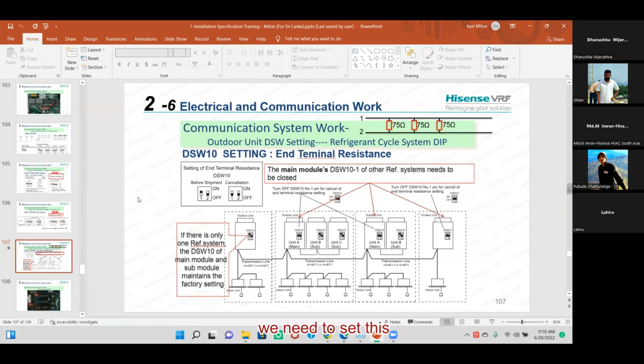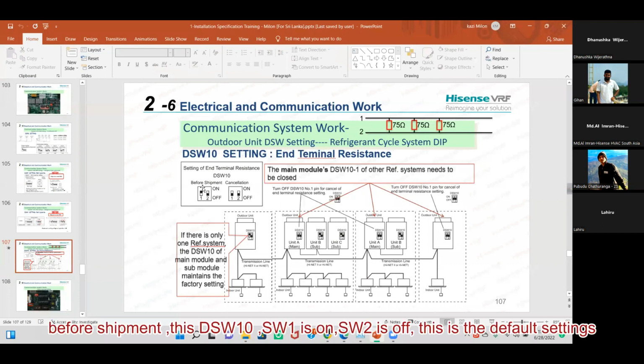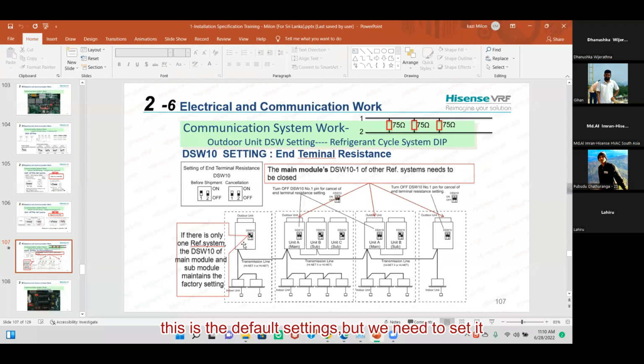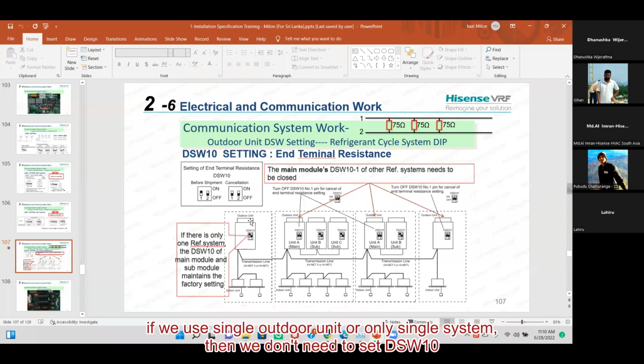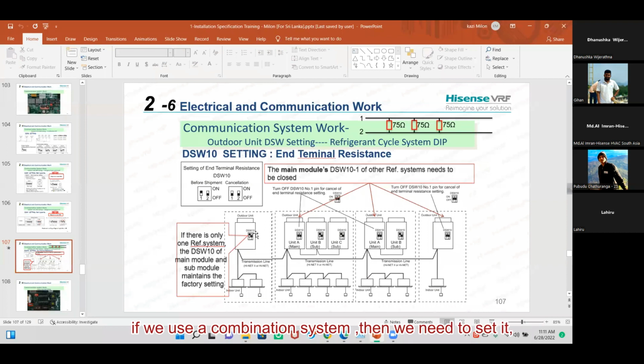Terminal resistance. We need to set it before shipment here. This DSW10 before shipment is 1 on and 2 off, and this is the default setting. If we use only a single outdoor unit, then we don't need to set this DSW10. But if we use a combination unit, then we need to set it.